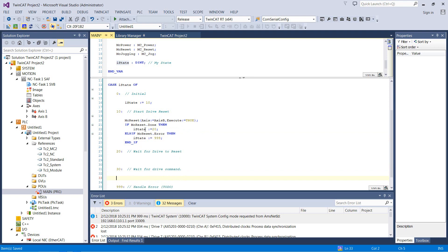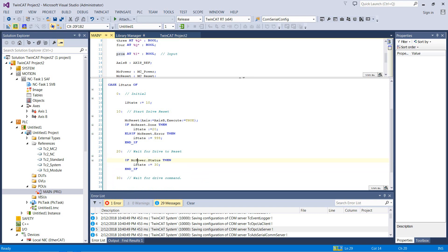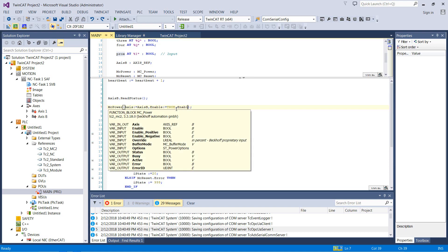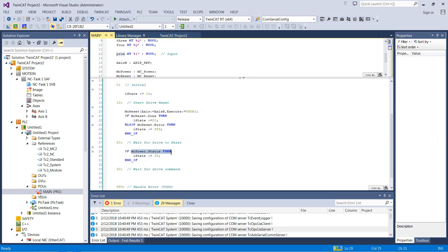So if this axis resets properly, it's going to jump to state 20, and we're going to wait on the drive to reset. What does a successful reset look like? In this case, if mc power dot status, then I state equals 30. MC power dot status will be true if the drive powered up successfully. With that said, we never told the drive to power up, so let's go do that now. We'll set enable equals true, enable positive equals true, and enable negative equals true. So once we do that, it should just always keep this drive enabled.